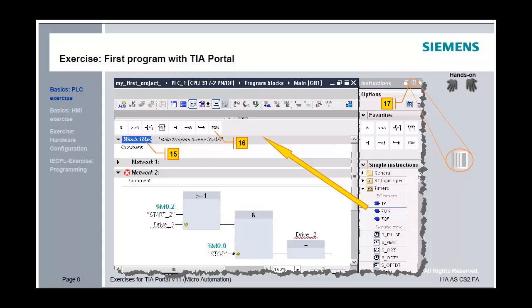Add an on-delay timer in Network 2 so that Drive 2 is activated 2 seconds after the request. Confirm the menu by pressing OK. An instance data block is automatically created.